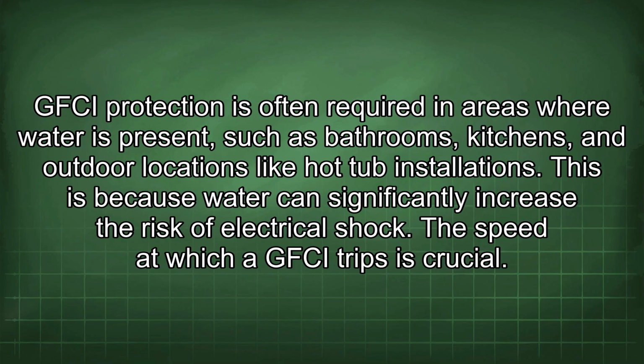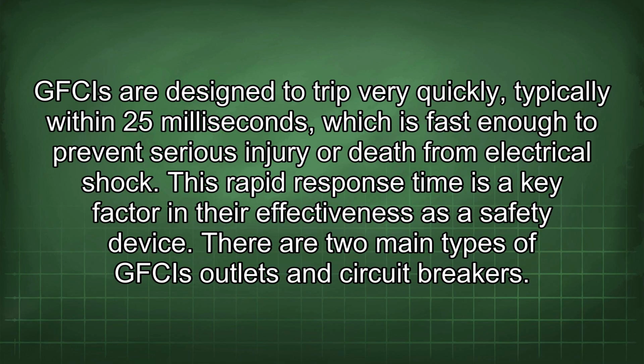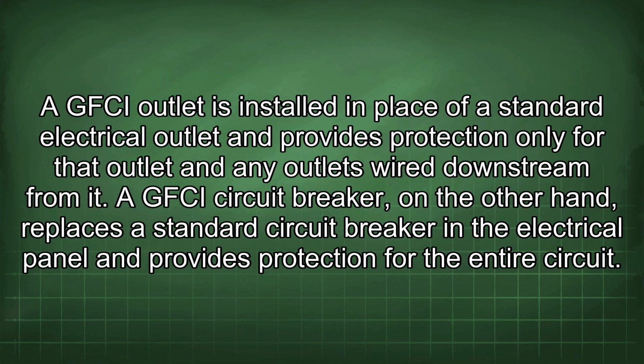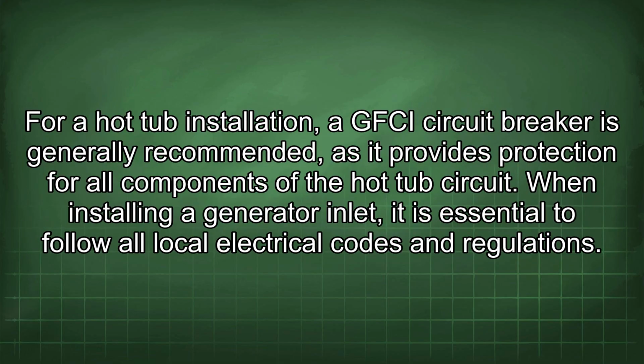The speed at which a GFCI trips is crucial. GFCIs are designed to trip very quickly, typically within 25 milliseconds, which is fast enough to prevent serious injury or death from electrical shock. This rapid response time is a key factor in their effectiveness as a safety device. There are two main types of GFCIs: outlets and circuit breakers. A GFCI outlet is installed in place of a standard electrical outlet and provides protection only for that outlet and any outlets wired downstream from it. A GFCI circuit breaker, on the other hand, replaces a standard circuit breaker in the electrical panel and provides protection for the entire circuit. For a hot tub installation, a GFCI circuit breaker is generally recommended, as it provides protection for all components of the hot tub circuit.